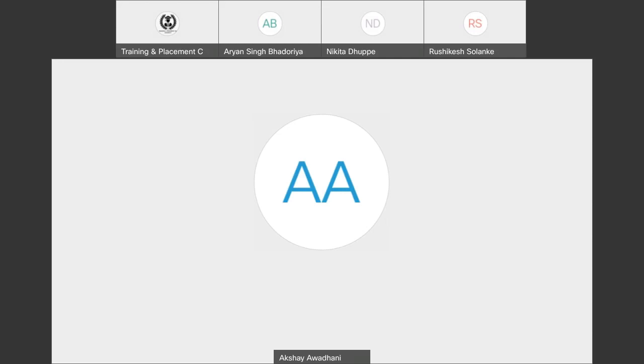Now you can contact the feeder 2 substation, explain the scenario, and ask how much load they can sustain. If they say you can add a maximum of 5 megawatts, then you can choose among the remaining loads which to put on feeder 2, because it was not giving us good voltage regulation. If we are expecting around 415 volts in 3 phase and we are getting 380 volts, that is definitely not a good, reliable supply. So we can add some non-critical load on that. We used to take that load off the local generation and put it on feeder 2 till then.